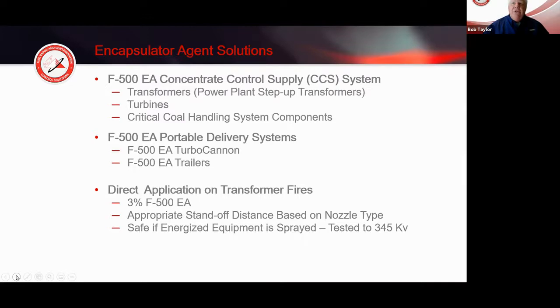So again, with encapsulator agent solutions, we do have the control concentrate supply system. It's used on transformers, both main transformers, GSUs, auxiliary transformers, substations, switch yards. It's really applicable anywhere - it's used on turbines, on some critical coal handling areas, not only within fuel handling areas like conveyors, but sometimes even in bunkers, silos, and bins. That type of system can be very effective on lube oil systems for boiler feed pumps and turbine generators - a powerful system to do many wonderful things that take the human element out of it and is recognized as highly efficient and successful.